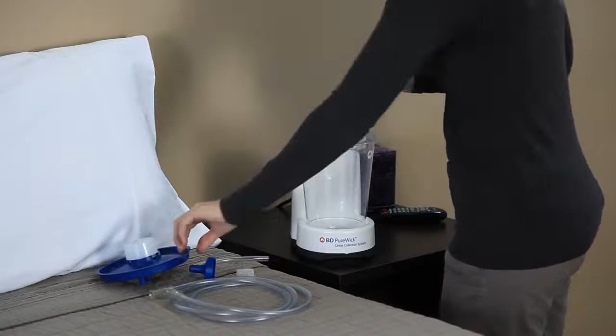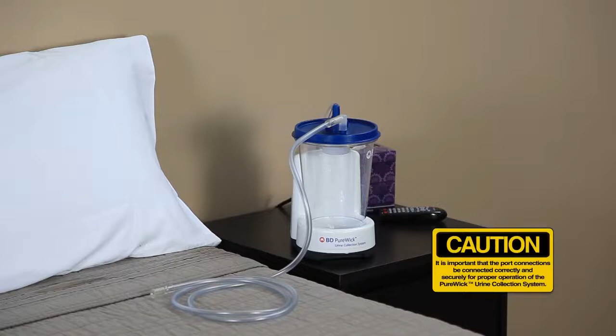Place the collection canister in the PureWick Urine Collection System base and press down firmly on the lid, making sure the lid is sealed. If using the privacy cover, slip the privacy cover onto the canister prior to placing the canister into the base. Attach the pump tubing to the PureWick Urine Collection System connector port and the connector port on the collection canister lid. Attach the elbow connector to the collector tubing. Attach the collector tubing to the connector port on the collection canister lid with the end that has the elbow connector.